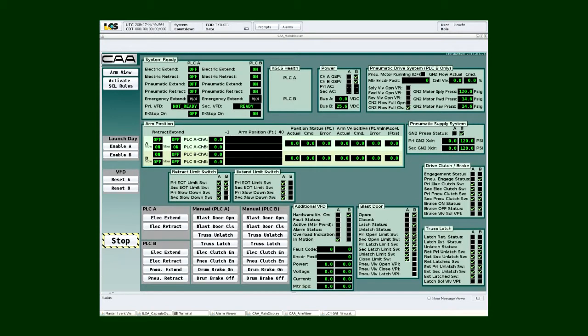Currently, the crew access arm is a critical system due to this requirement, and it has both redundant hardware as well as redundant control systems. And if we take a quick look at our screen, you'll notice that we have PLC A, which is the programmable logic controller on the A stream, and we also have information for PLC B. Like I was mentioning earlier, the crew access arm is a redundant system, so it has an electric drive system as well as a pneumatic drive system.